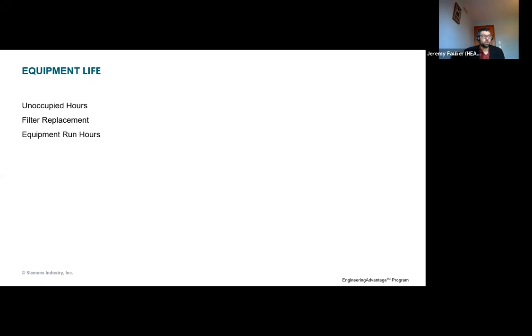If you're looking at just increasing outdoor air, that really has a marginal impact on equipment run hours. Your equipment's still going to have to turn on for cooling at about the same outdoor air temperature. If you're in cooling, maybe a little bit sooner, at a slightly cooler temperature, because you've got just more outside air brought in. And if you're in heating, you'll probably have to bring it on at a slightly warmer temperature, just because of the greater quantity than you otherwise would have. But I would anticipate a marginal amount of hours being run.